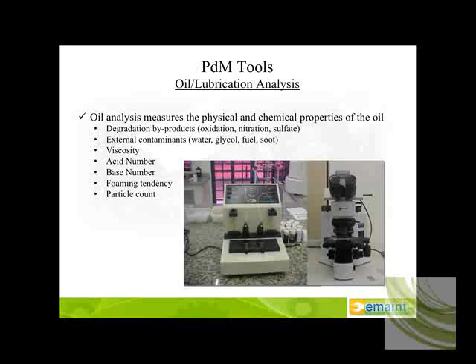Sampling techniques are fairly critical. The equipment should be at an operating temperature when drawing that sample. Sampling should be done, of course, during operation while that asset is running. The sample should be representative of oil in the system, never from a dead leg and never after the filter. Naturally, if you're taking it after the filter, you're filtering out the particulate matter, the issues that you're looking for within that oil. So we want to take it where it's representative of the operating conditions of that oil.